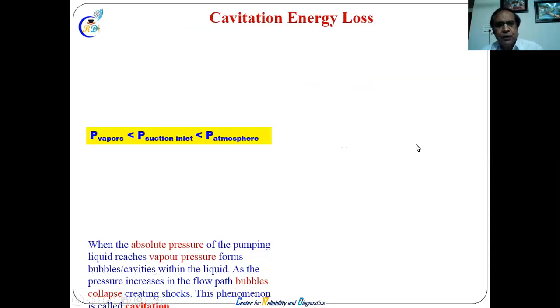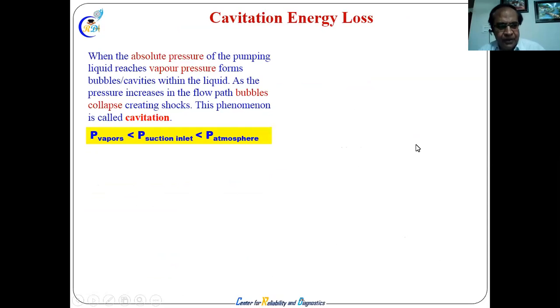In pumps, we get a lot of cavitation. And somebody asked me, sir, can we prevent cavitation? It is possible to prevent cavitation if you maintain it properly and operate it properly. So there is always a possibility. So, the absolute pressure at the inlet. See, this is all the definition of cavitation. No cavitation means vapor pressure must be less than suction inlet pressure, and must be less than atmospheric pressure.